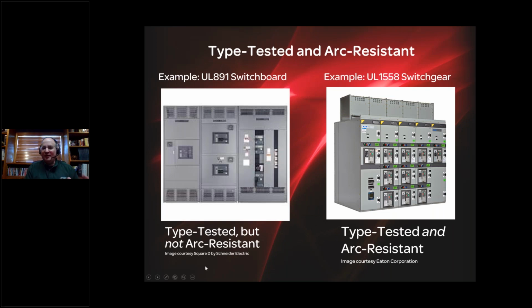So when we compare type-tested equipment to arc-resistant, on the left, I have a switchboard, which is just a standard non-arc-resistant switchboard. And how can you tell that? Well, look at all the vents on the front that could vent hot gas and plasma out the front of that switchboard. Now, again, none of the covers and the enclosure itself can rupture, but it could definitely eject hot gas and plasma. On the right, we have an example provided by Eaton Corporation in the picture that shows type tested and arc resistant. Okay, so notice no vents out the front of the equipment.